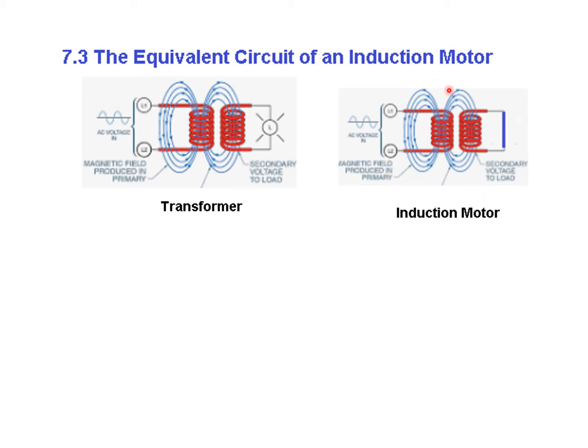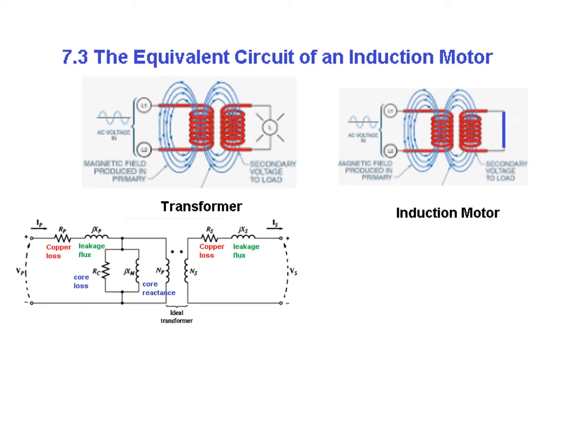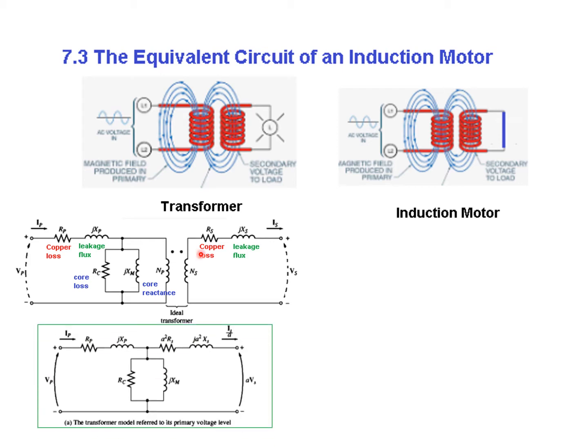To understand the equivalent circuit of an induction motor we will take help of the equivalent circuit of a transformer. The transformer equivalent circuit is represented with the copper loss and leakage flux on the primary side, and the core loss and core reactance. On the secondary side we also have the copper loss and leakage. To solve this, we transform either the primary circuit to the secondary or the secondary to the primary side. The resultant circuit has the secondary side transformed to the primary side, multiplied by the transformation ratio. A similar circuit applies for the induction motor.